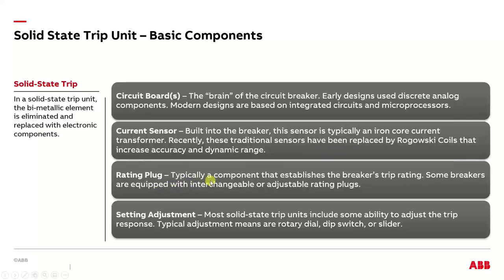Sometimes there would be a rating plug. And so when you figured out what your nominal trip value is, it was usually, okay, I've got a current sensor in my breaker of 200 amps, and my rating plug is an 80. So the rating plug is where the breaker would trip. And sometimes those were interchangeable. So you could have one breaker with interchangeable rating plugs that you go from 50 amps to 250 amps. Range pretty widely throughout the industry.